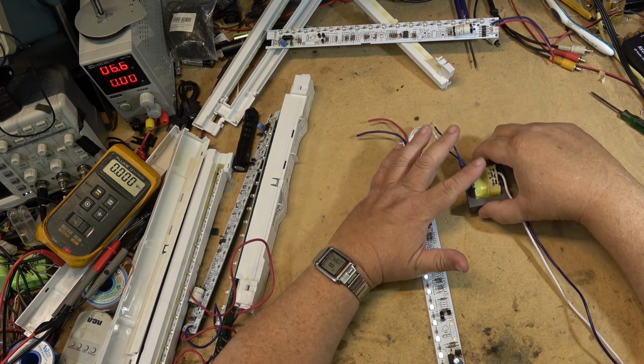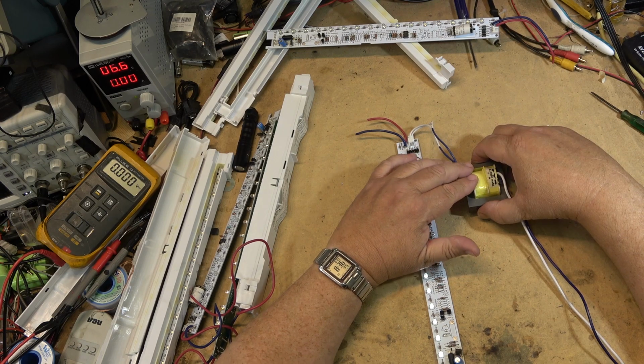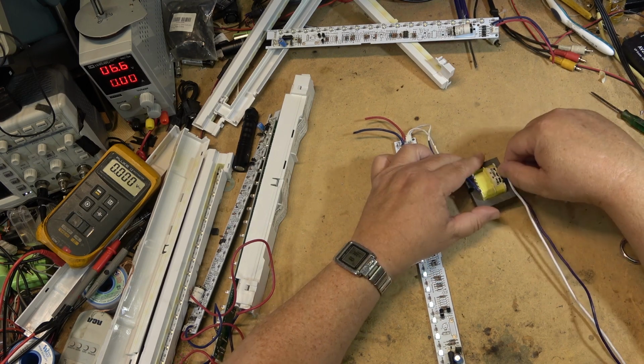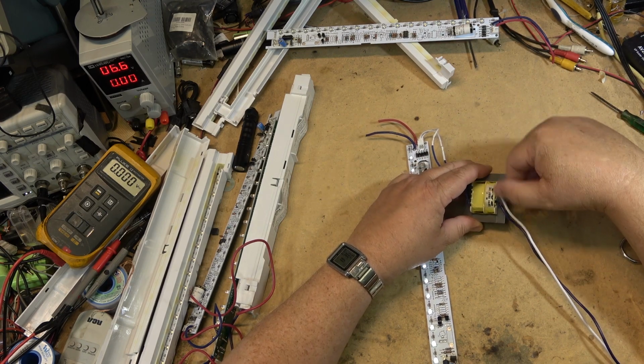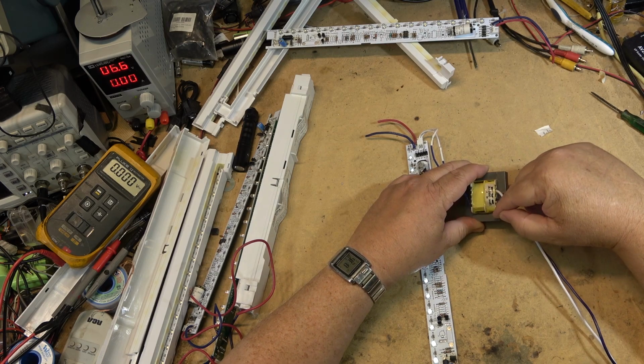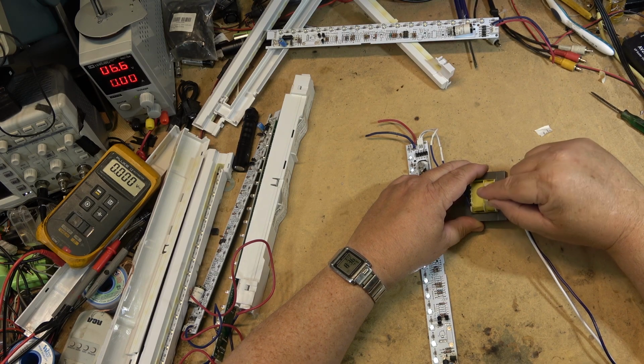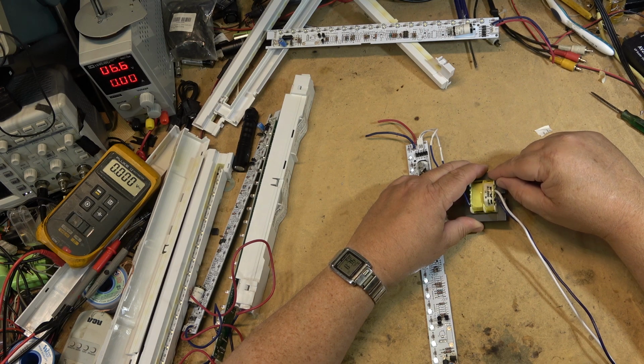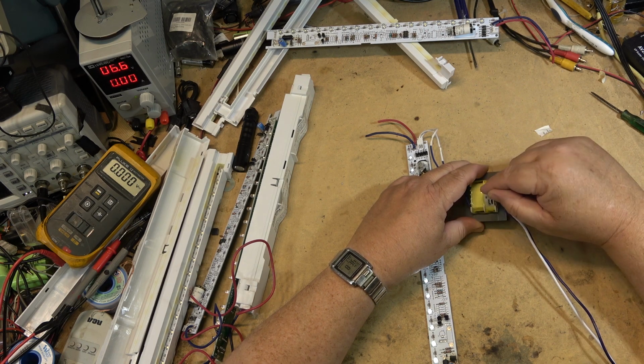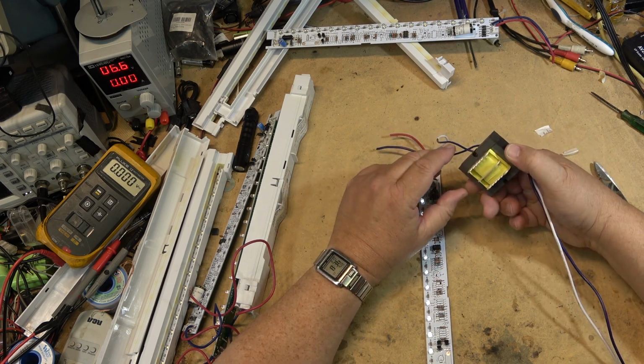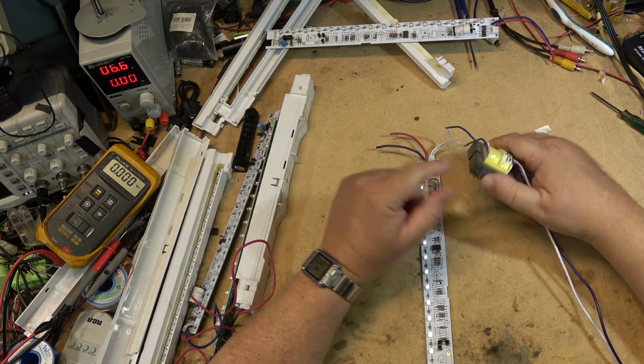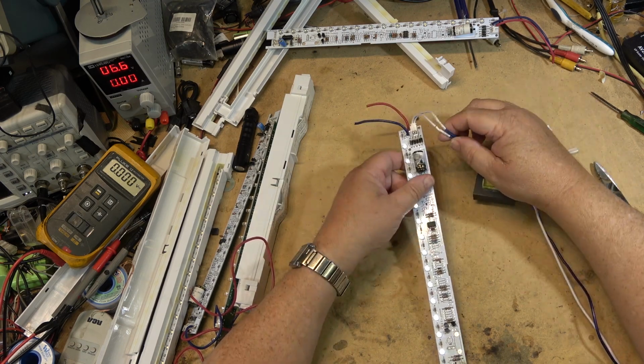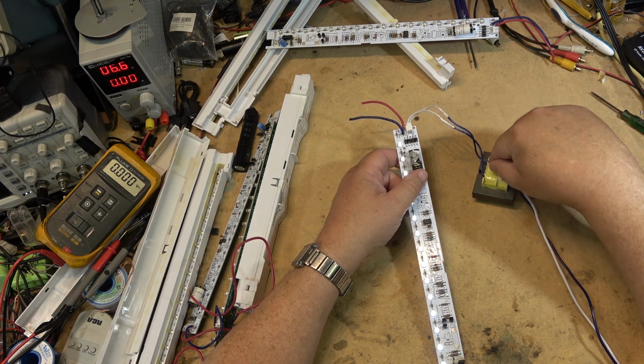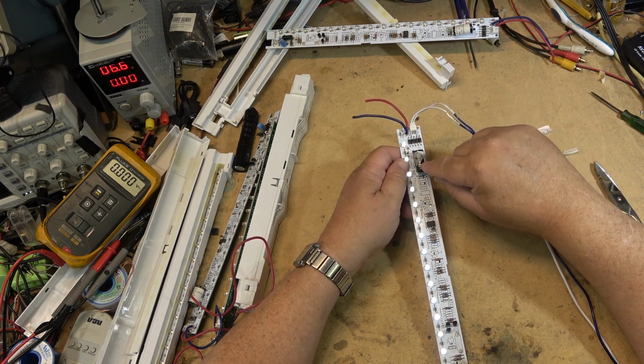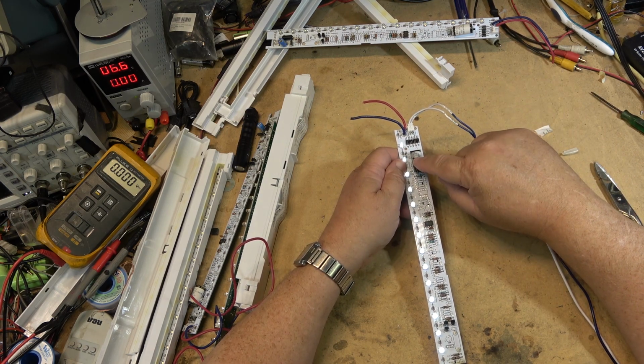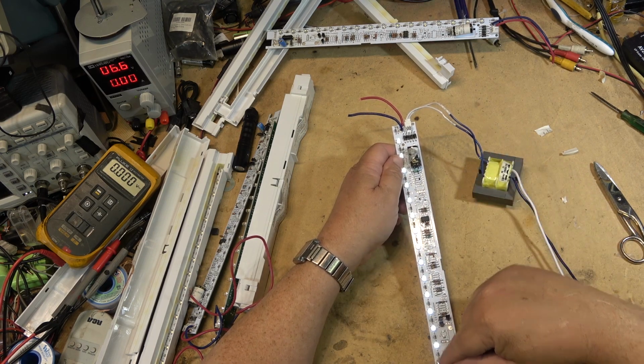I've seen some of these exit signs - I saw one a while back. Somebody gave me a couple that actually had separate taps on the transformer. It had multiple wires, and you would connect one for 120, one for 208, and one for 347. It actually had 3 separate windings on the primary. These ones here have a single winding on the transformer. The output will vary depending on what the input is, and that's going to affect the DC voltage on the capacitor, which is required to be regulated for the LEDs.